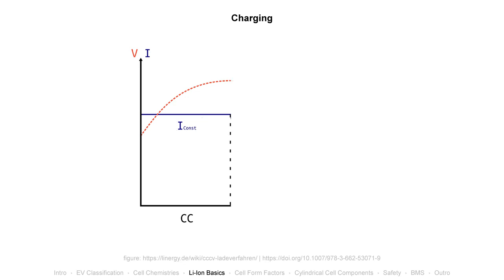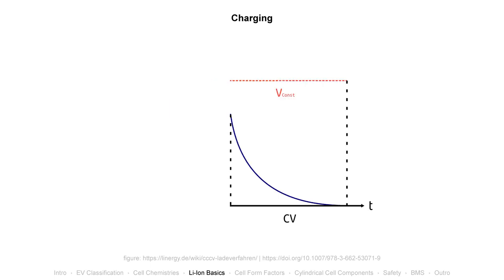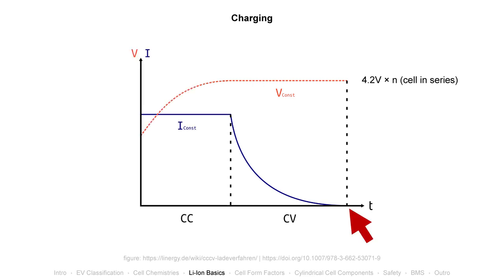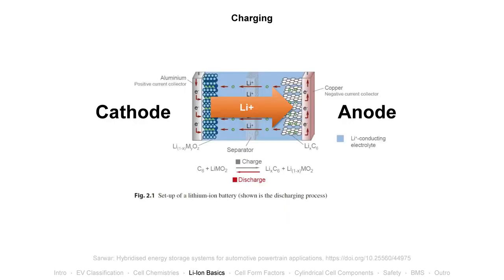When the battery is in a low state of charge, constant current is applied to the battery. When the corresponding voltage reaches the fully charged voltage, it is kept constant. The current then slowly decreases. Once a time limit or the threshold of minimum charging current is reached, charge should be completely terminated. This charge termination current is specified in the cell datasheet. The cell is now fully charged.